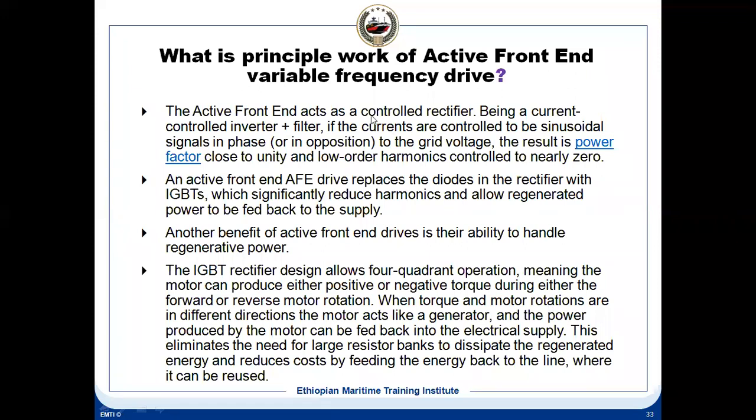So this is what the active front end is. Some of them you'll find like VFD, this is active front end. Active front end means the front end is active. There we are using transistors, IGBTs, thyristors, etc. So active front end drive replaces the diodes in the rectifier with IGBTs. Okay, active front end replaces the diodes in the rectifier with IGBTs, which will significantly reduce the harmonics and allow the regenerated power to be fed back to the supply.